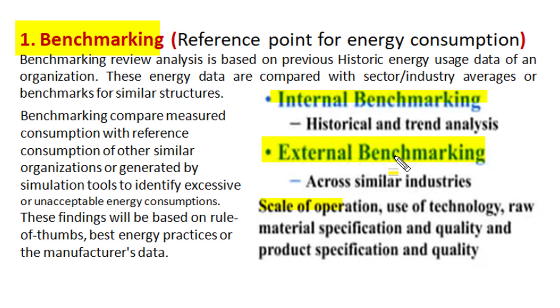Benchmarking compares the measured energy consumption of any industrial plant or service organization with the reference consumption of other similar plants or organizations. Many a time we use computer simulated information from appropriate computing tools to identify any excessive or unacceptable energy consumption in our organization. These findings of benchmarking, or reference standard points of energy consumption, are many a time based on rules of thumb from previous experience or best energy practices in our sector, or we use manufacturer or supplier data for the equipment which we are using in our plant for benchmarking purposes. And if in benchmarking we find energy consumption in our organization higher than the set reference points, then it needs further investigation by either a preliminary walkthrough audit or a detailed energy audit.